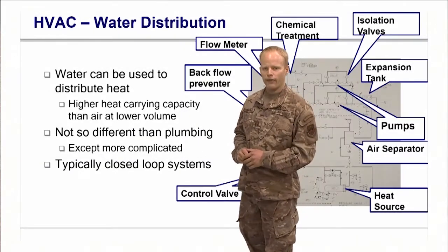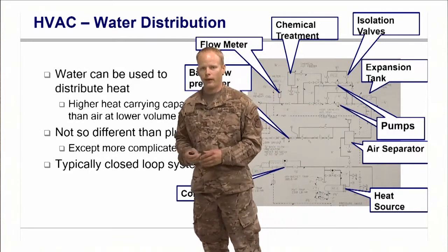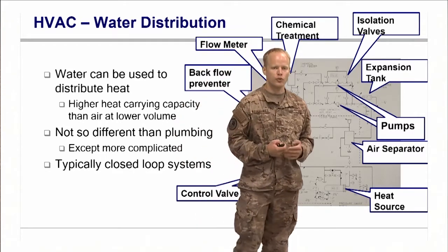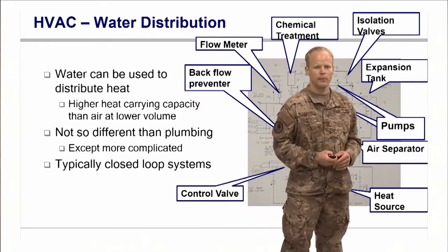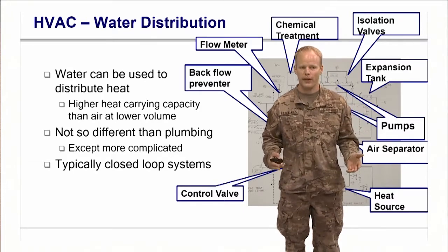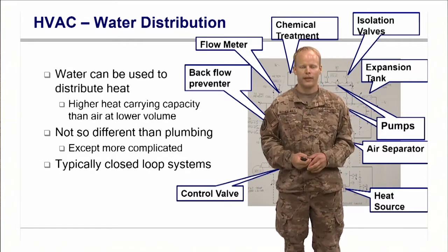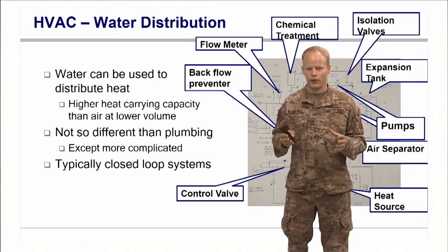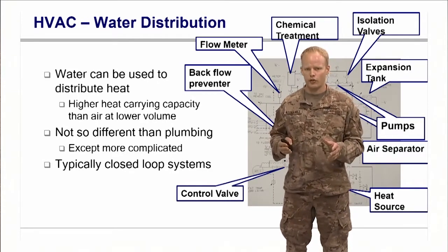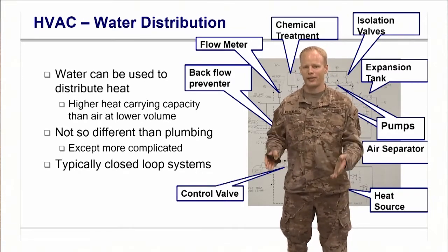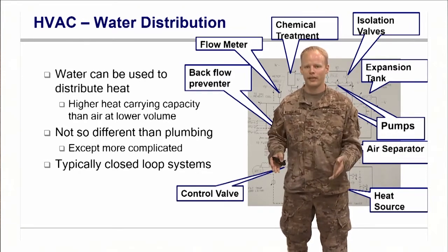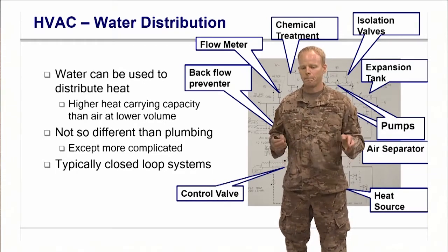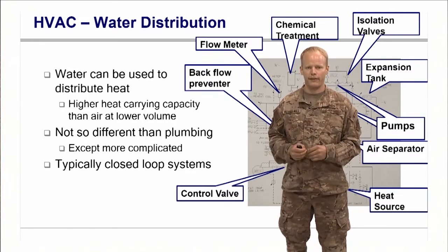So now that we have the water, it's been chilled, we have to move it to where we want to use it. We use water in a lot of cases because water is much better for moving thermal energy than air. We like air. Traditionally, we like air because air is very useful. In the end, in your zones, we treat the air. We do air conditioning. We don't do water conditioning. So we like to distribute air to the zones because then we can mix it, and that's what you and I feel.